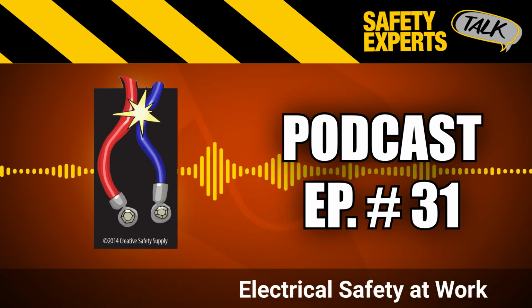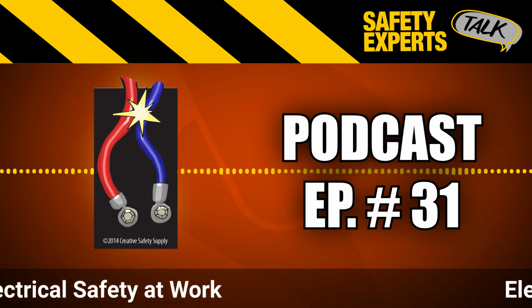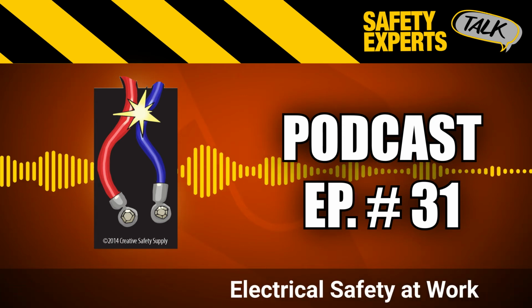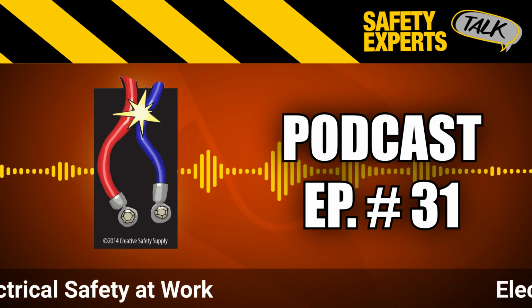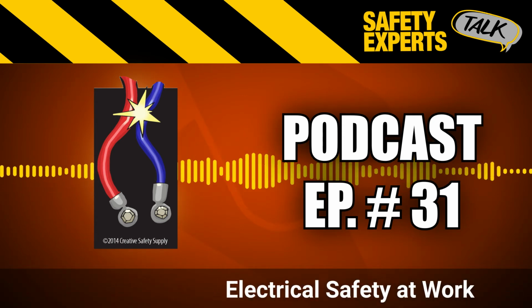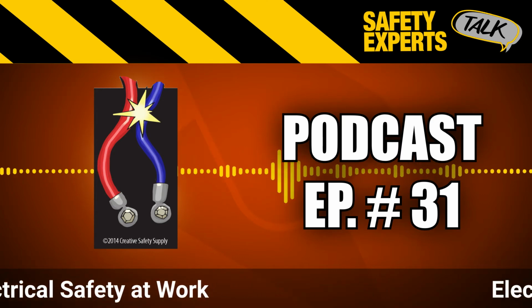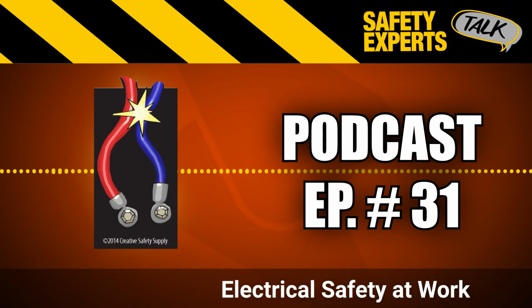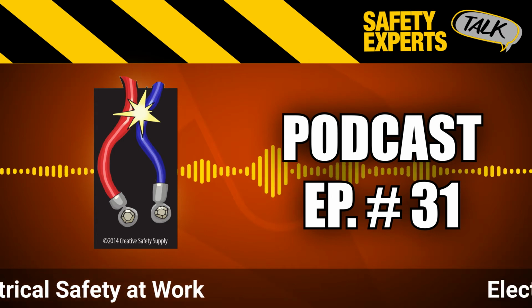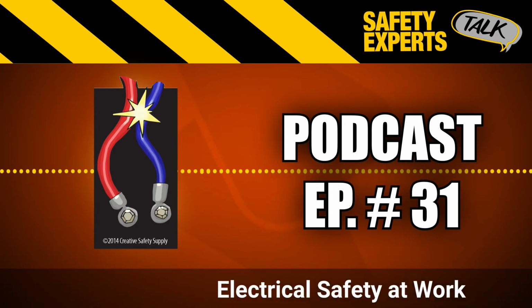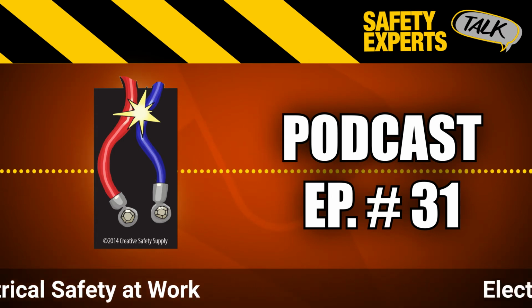At the bare minimum, arc flash labeling should contain the incident energy, meaning in calories per centimeter squared, how intense that energy blast will be, and the proper working distance the qualified person should work from, usually 18 inches.